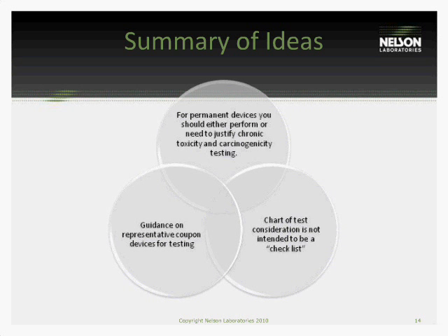So basically we can take whatever material you have in your device and make it into a coupon, which is maybe a square or some kind of thin sheet, something that might represent your final device, but we don't need to test a functional device. This is also beneficial for devices that have internal components that are not patient contacting. So electronic components, other wires, things like that that may be in the device, but we don't necessarily want to test them. We can actually test a coupon that does not incorporate those materials.